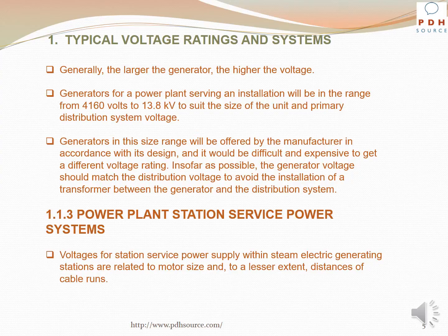Generally, the larger the generator, the higher the voltage. Generators for a power plant serving an installation will be in the range from 4160 volts to 13.8 kilovolts to suit the size of the unit and primary distribution system voltage. Generators in this size range will be offered by the manufacturer in accordance with its design, and it would be difficult and expensive to get a different voltage rating. Insofar as possible, the generator voltage should match the distribution voltage to avoid the installation of a transformer between the generator and the distribution system.